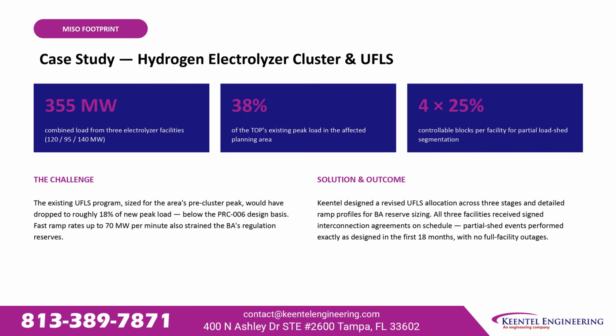Our third case study, 3 hydrogen electrolyzer facilities totaling 355 megawatts, or 38% of the area's existing peak load. The existing under-frequency load shedding program, sized for the old peak, would have dropped to just 18% of the new peak, below the required design basis, and ramp rates up to 70 megawatts per minute strained the Balancing Authority's regulation reserves. We redesigned the load shedding allocation across 3 stages, segmented each facility into 4 controllable blocks, and built detailed ramp profiles for reserve sizing.